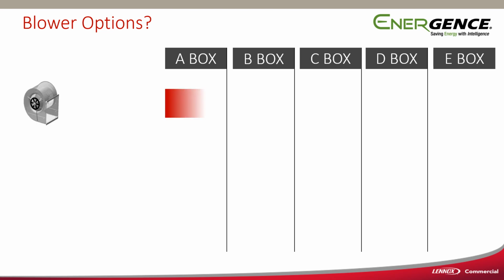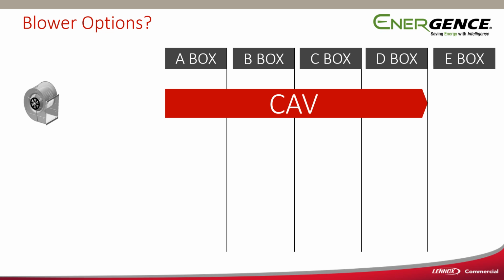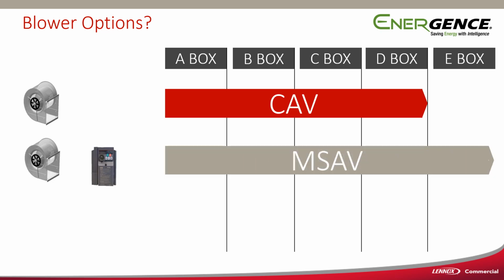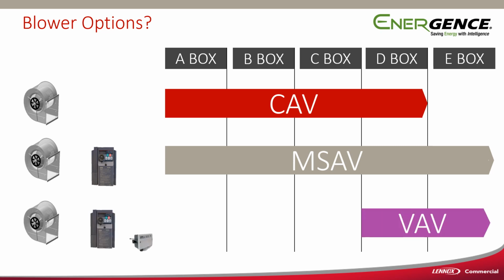Now the blower options on these units, we have constant air volume is an option on the A, B, C, and D. The E box does not have that option. We have MSAV on the entire product line, A, B, C, and D, and the E box, it's standard. We have no choice. We traditionally did the D box and the E box as a variable air volume system. We now do that down into the C box. So we do C, D, and E box with variable air volume.